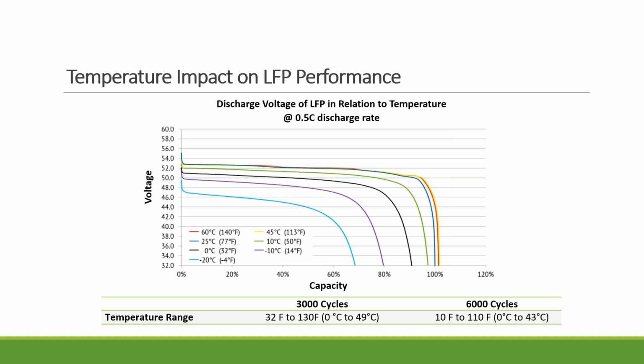And the other important factor is temperature. Now, this is a typical graphic of how LFP chemistry reacts to temperature. 25 degrees, 77 Fahrenheit, is basically the benchmark here. And as you can see, on the high temperature end, LFP chemistry actually does very well. The capacity is very consistent. Where you start to worry is when you are using the battery below freezing temperature. Then you're going to see the capacity drop, and of course the cycle life is going to drop. So we really recommend that you put it indoors, or if you're in a warm area, like the Central Latin American market, you can certainly put it outdoors, but make sure it's not directly exposed to the sun. So have a container or put it under a shed.